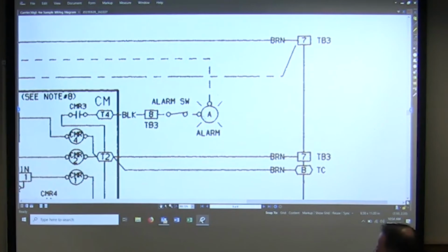So if I put either an audible or a visual alarm here, what type of alarm does it need to be? 24 AC, right? Okay, and so it shows that I'm going from TB8. Is this switch included, or am I adding that? It's field installed. So probably field installed because there's a little gap on either side of it. Again, they could have stretched this over a little bit to give us a little more dashed line, but my guess is the switch and the alarm are field installed. Okay. All right.